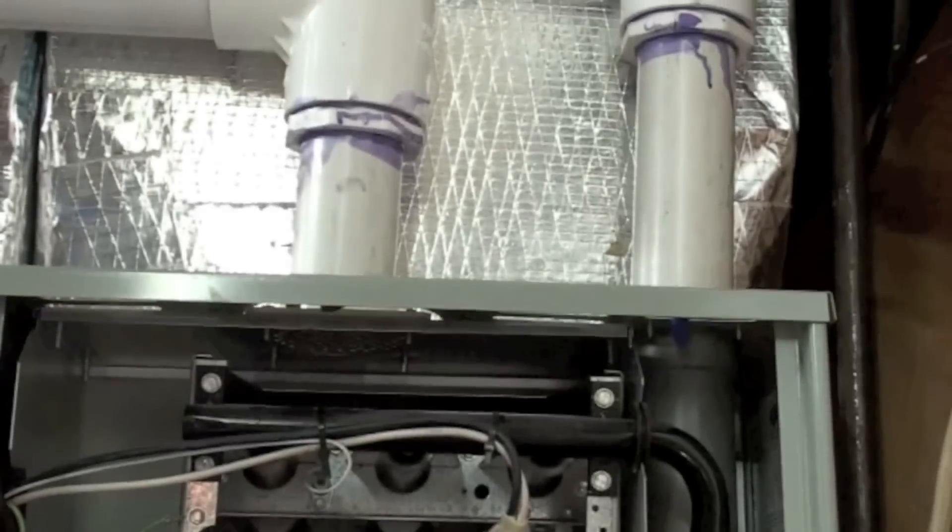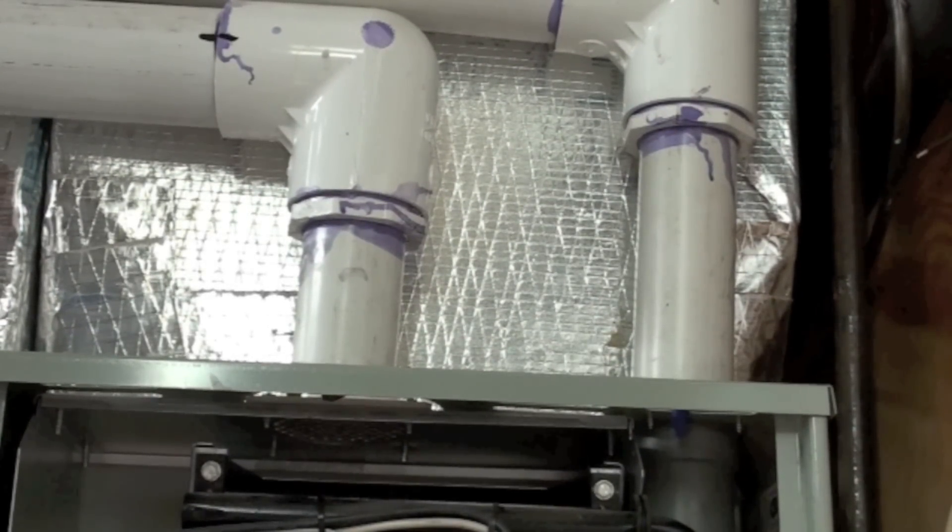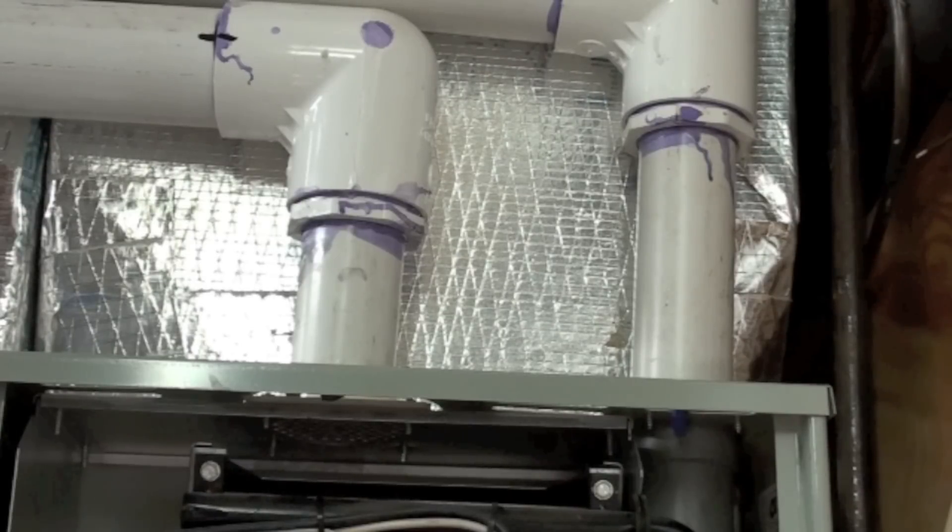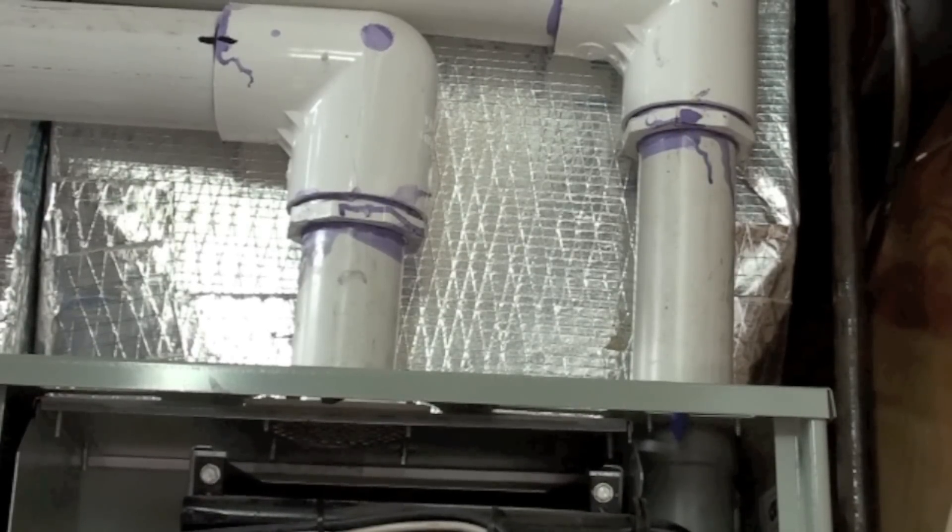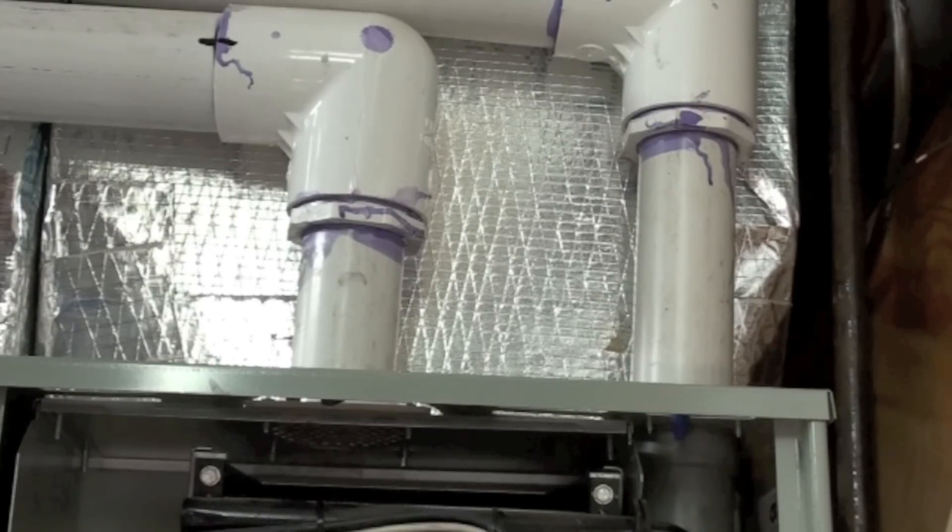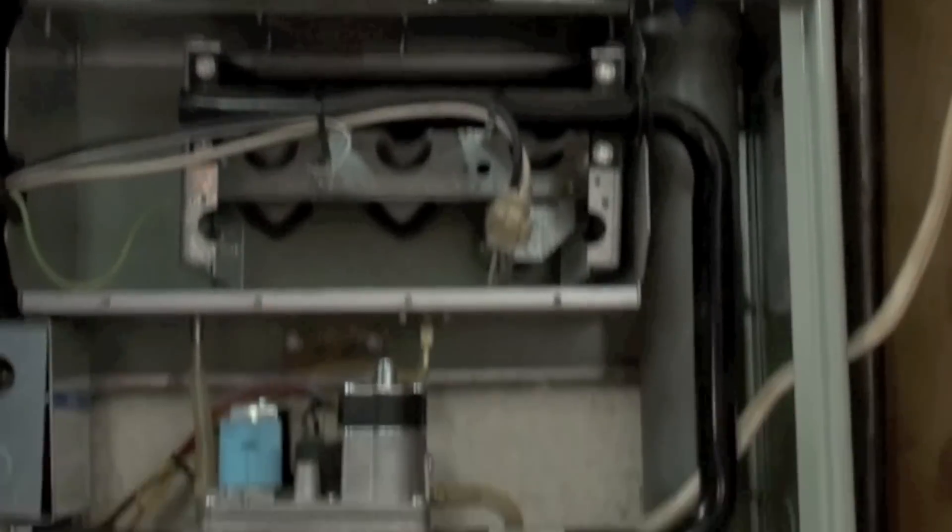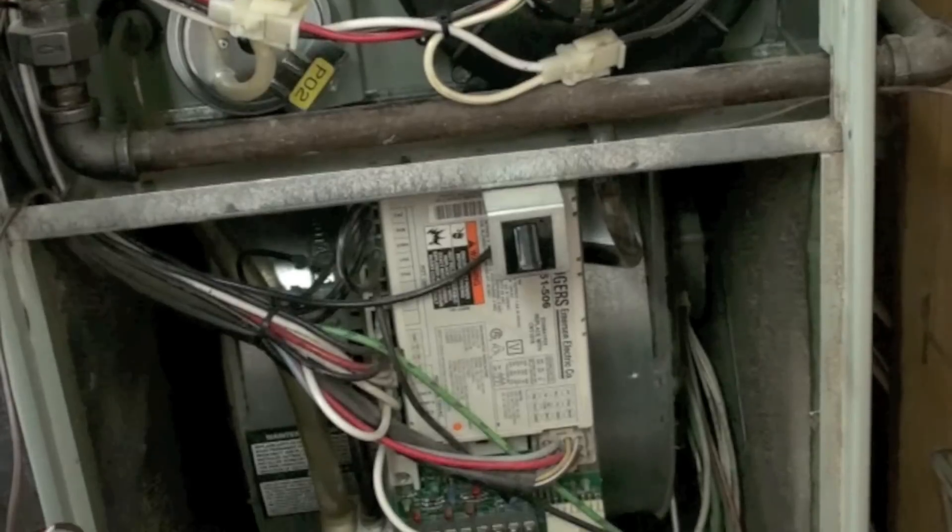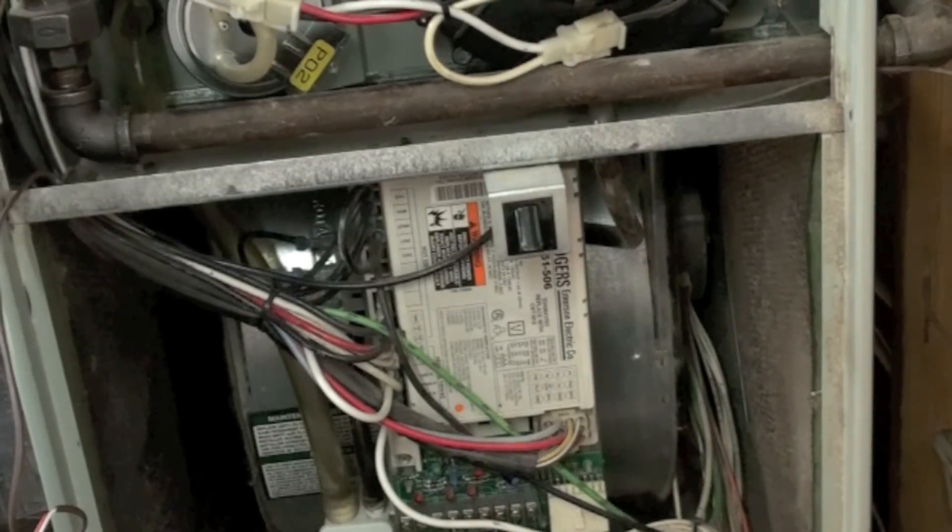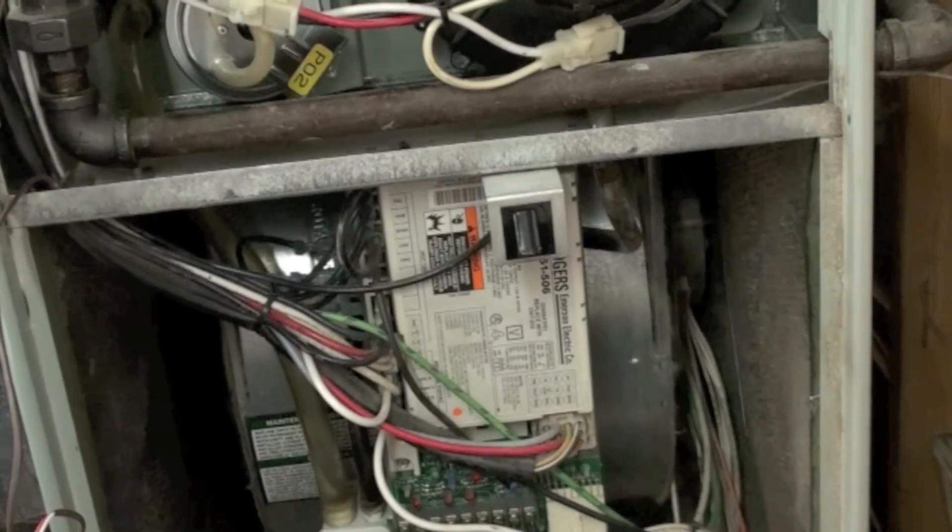Venting on these plastic vented furnaces, these 90s, if it doesn't pitch towards the furnace, then sometimes you'll get intermittent shutdowns there. So look for that, listen on the pipe, put a screwdriver up to the pipe.